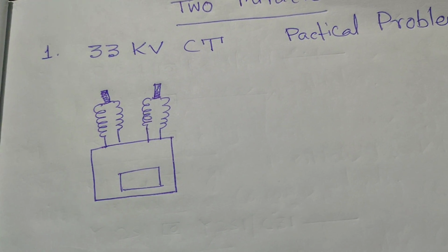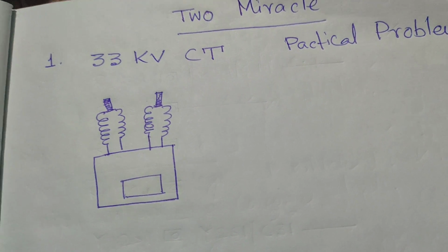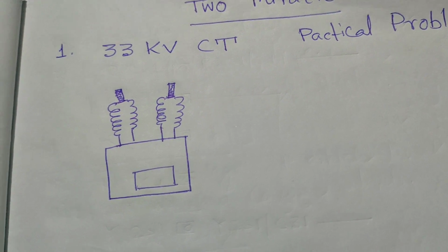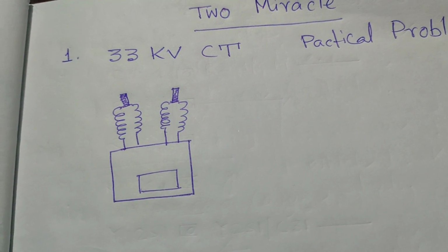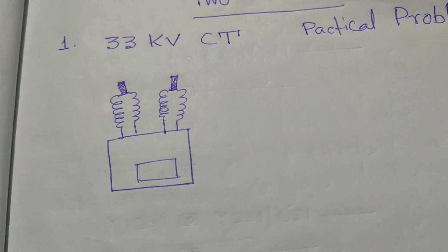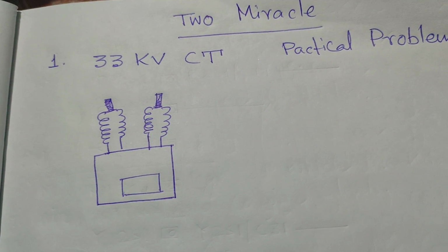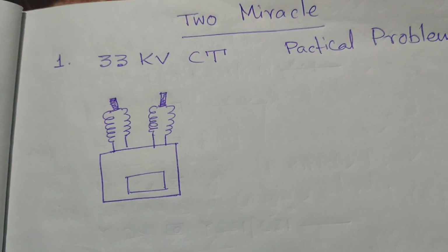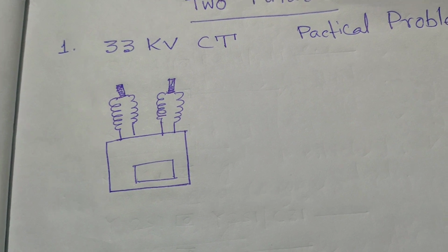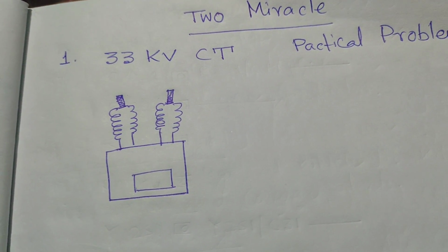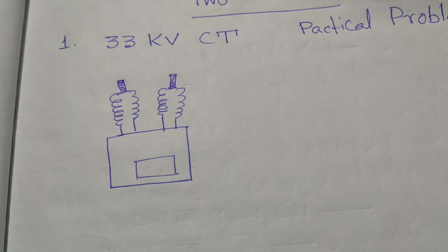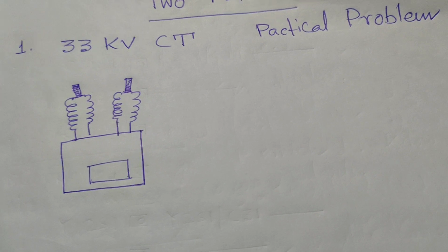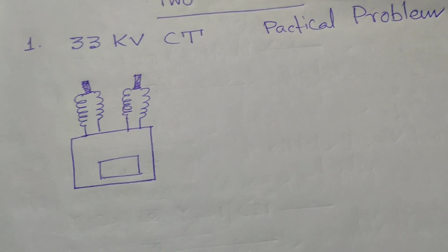The damaged CT ratio was 400 by 200 by 1/1 3-core CT, and we replaced that particular CT with an 800/400 by 1/1 CT. After proper testing, first the polarity test, second the current injection test, we confirmed that the CT is now in okay condition. So we replaced the CT and then charged the line accordingly. No problem. That was my first problem.